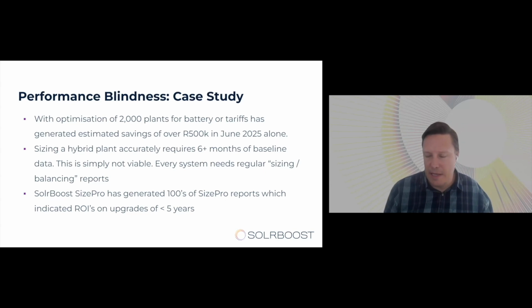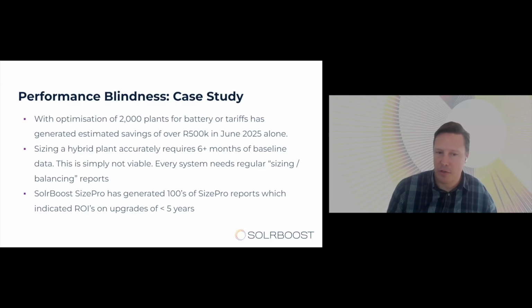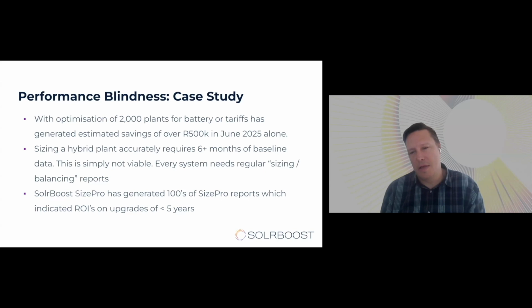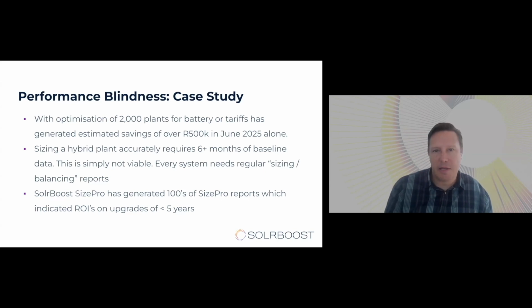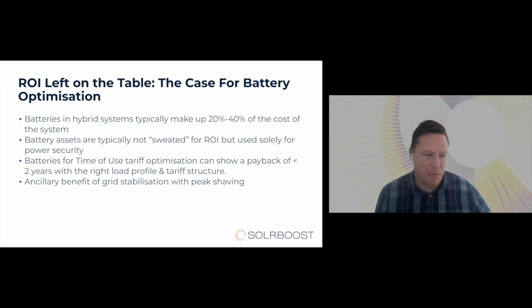We've got a product called Size Pro, which effectively does this. It looks at historic load patterns and various external factors, like weather, and then gives you an indication of what the correct sizing of a plant should be, given the actual data that you're running. It's effectively like a digital twin, one of the terms people use for it, where we create a digital twin of your plant and then simulate different scenarios with it. Our Size Pro product has generated hundreds of reports which indicate that certain battery or PV upgrades would have an ROI of less than 5 years, which is a very compelling financial case to be made for that upgrade.